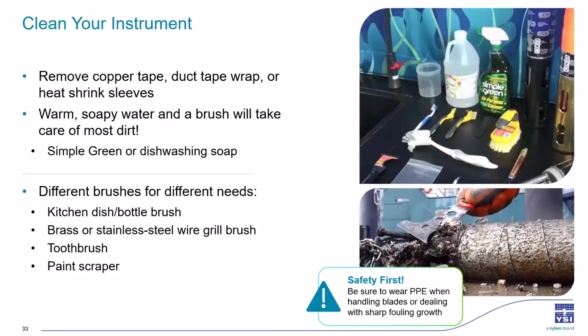Even a grill brush, wire brush is helpful to clean off anything that's stuck on the outside of the sensor. Obviously, be very careful not to damage anything if you're using a wire brush. A toothbrush can help get around sensors as well as the connectors, but mind the sensor tips. We generally don't want to be scrubbing them. And then if you're having a really tough time, you could even resort to a paint scraper to remove mussels or barnacles, let's say. But be very careful if you're using anything sharp.